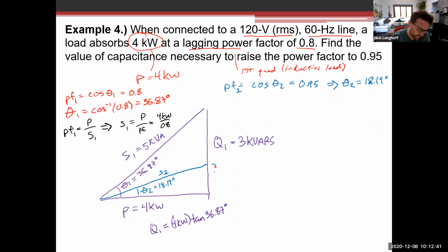We are interested in the reactive power Q2 that we need to get to. The total reactive power will be 4 kilowatts times the tangent of theta 2. When we put that in, we find this is 1.3144 kilovars.